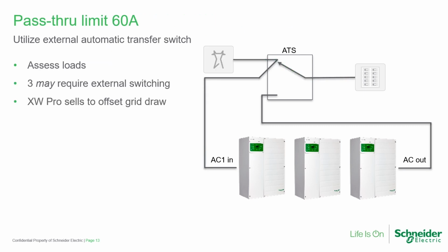A single XW Pro system can supply 28 amps of continuous current. A dual system can supply 56 amps and a triple can supply 84 amps. Single and dual systems do not require an external transfer switch. However, triple inverter systems may require an external transfer switch. The designer must consider the maximum surge requirements of any motor loads. A single-phase motor can draw up to 7 times its continuous rating for startup.